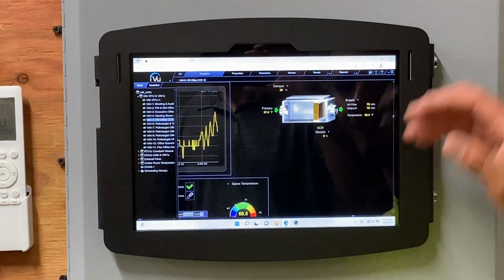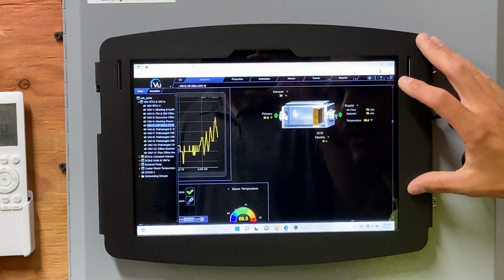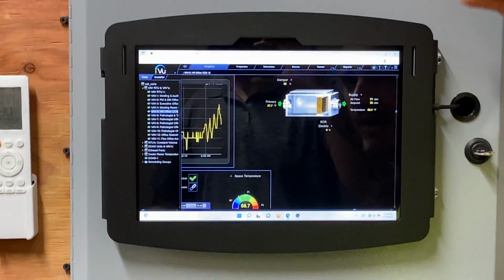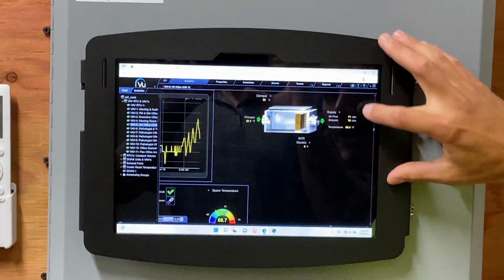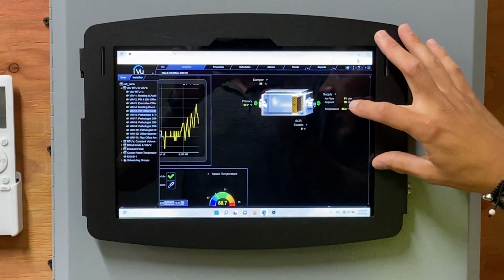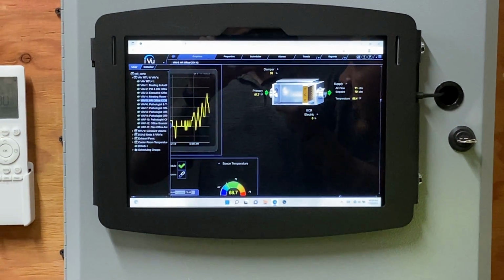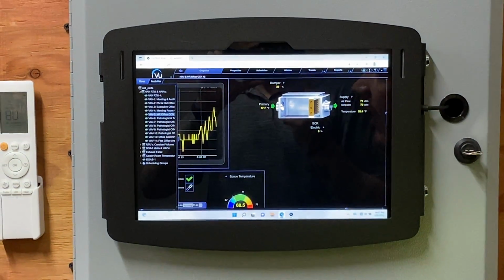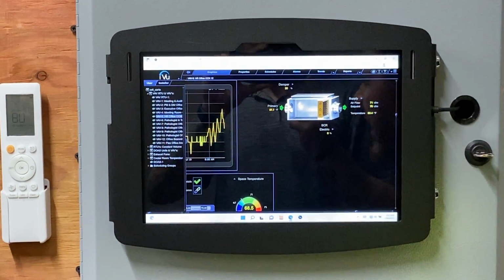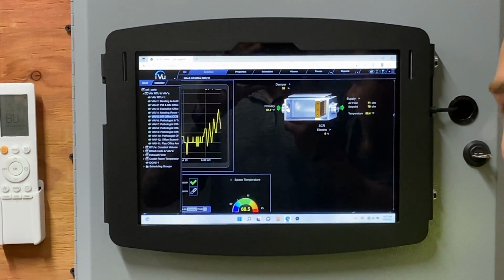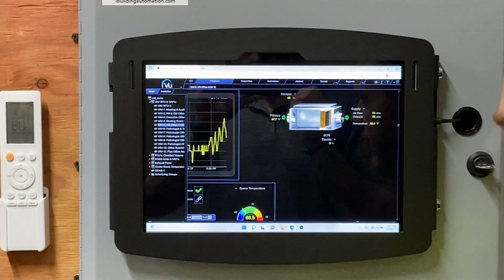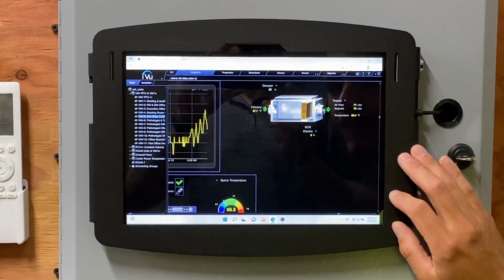So that's about all you're going to see on a VAV unit. When you're referencing a VAV, you want to ask: do I have damper percentage and do I have flow? And then obviously we're going to check our outlet temperature. Those are going to be the most important values we're looking at, because if we don't have flow, then the box is not going to operate, the same way as if we didn't have fan on, stuff like that. That's our main value: flow.